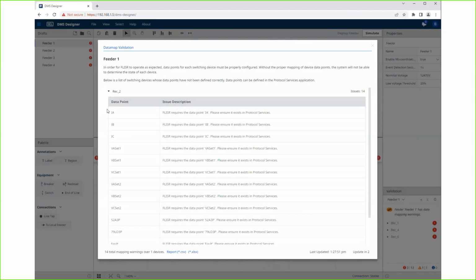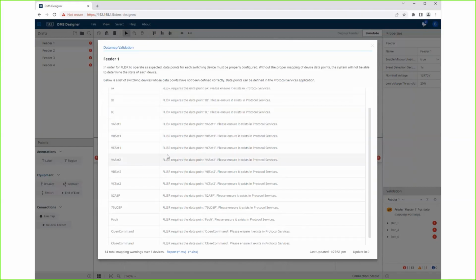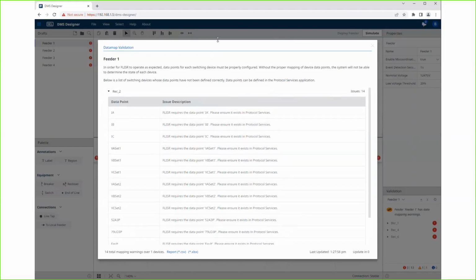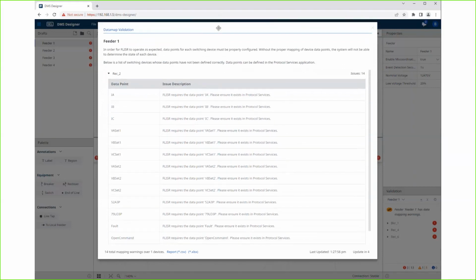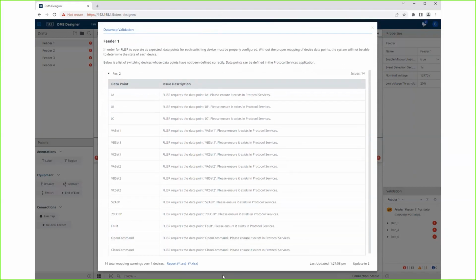So it finds the Rec2 connection and it starts looking for things like three-phase current, voltages, breaker status, lockout, fault, open and close command, and it doesn't find any of them because we haven't created any of those in the DNP connection. But it does tell you exactly what it's looking for, and you can export that as a report. So you can export it as a CSV or as an Excel spreadsheet to make it easy to keep track of what FLISR is looking for.